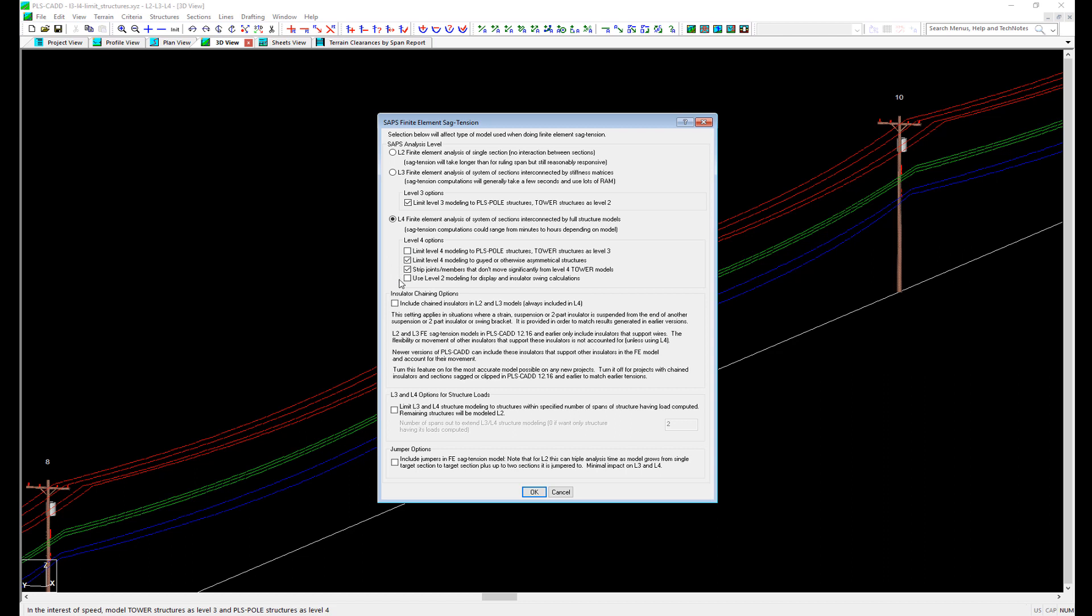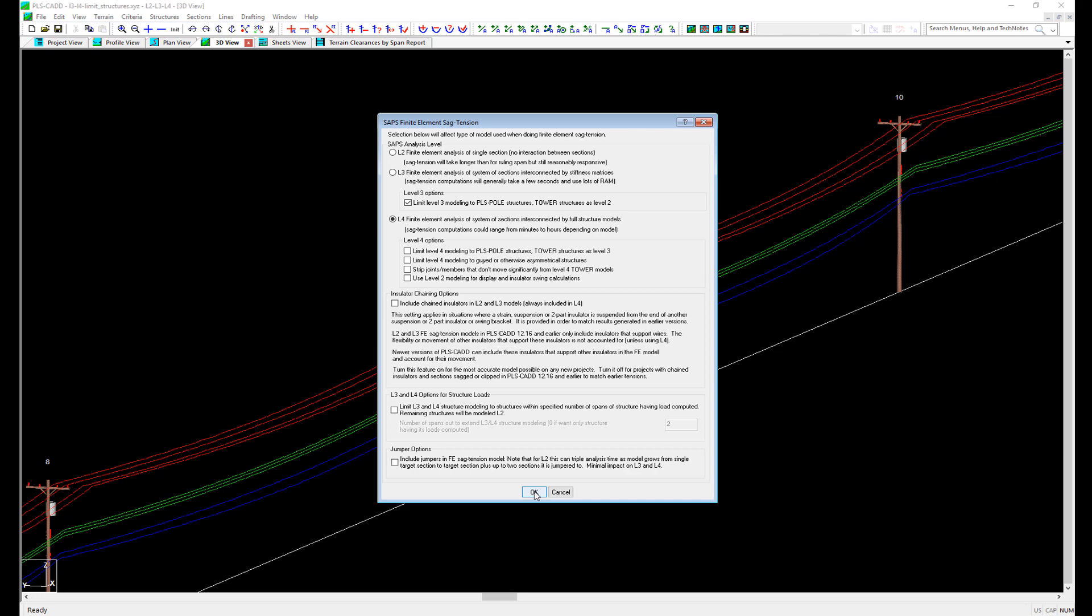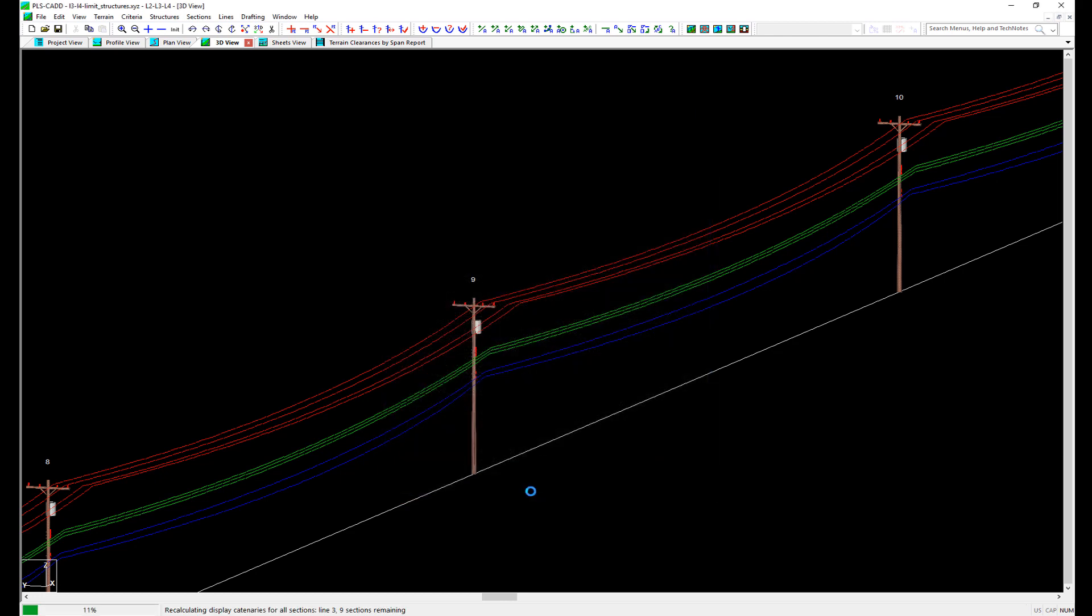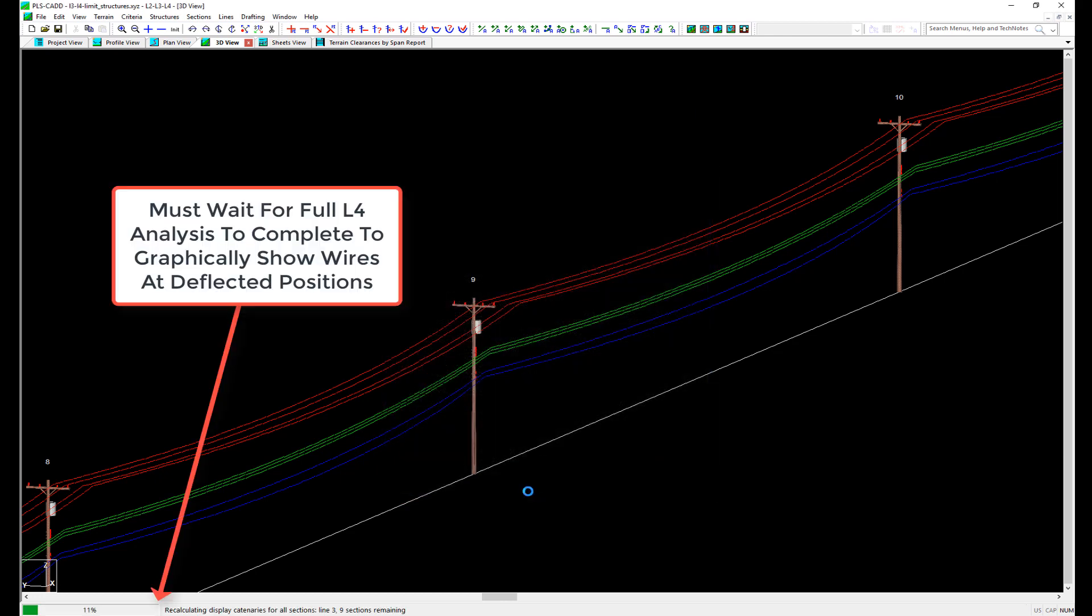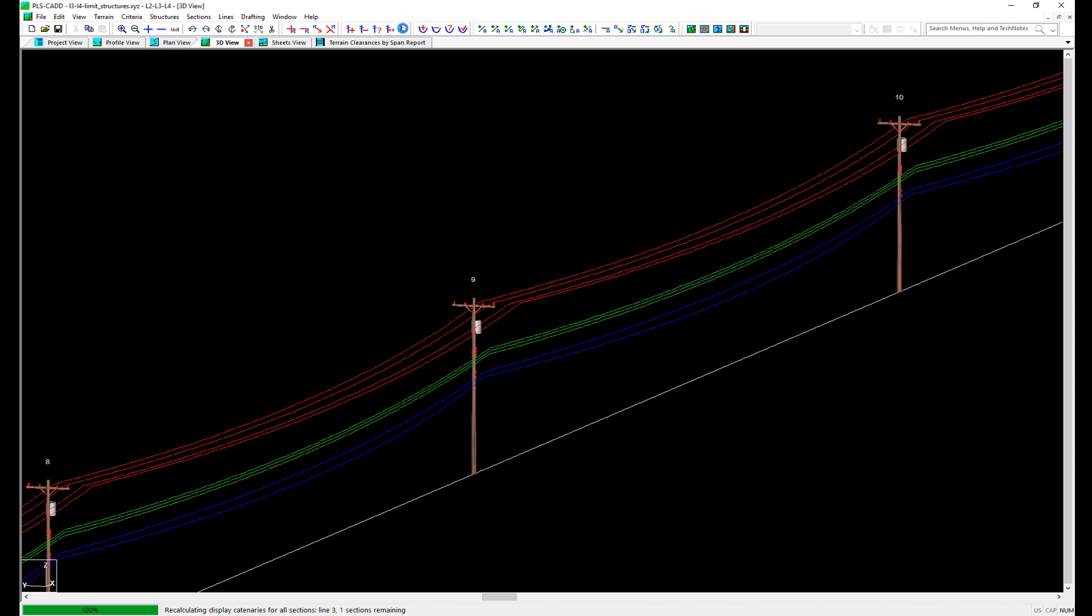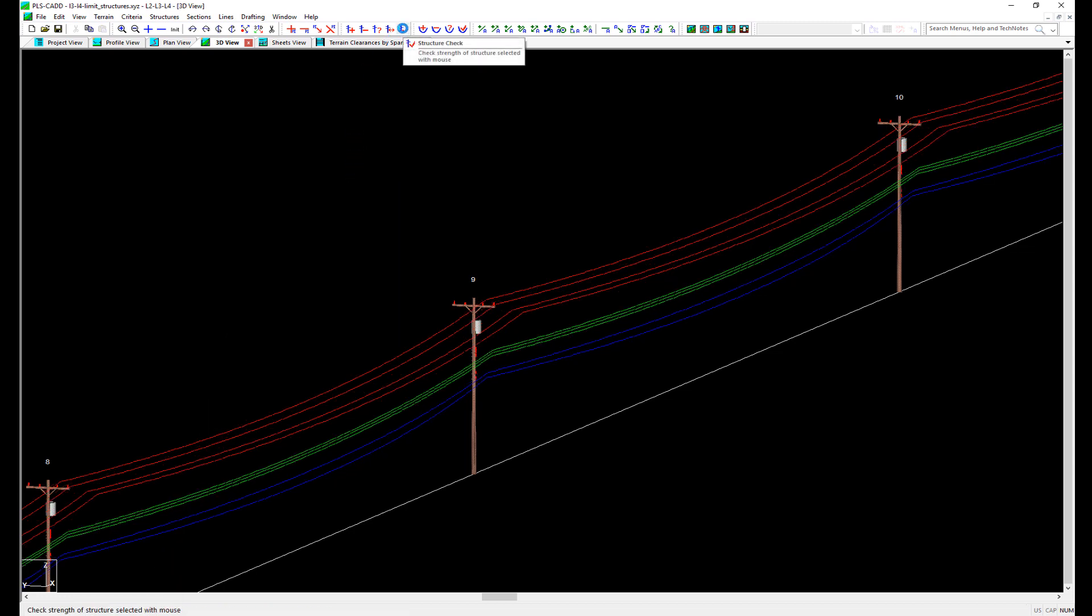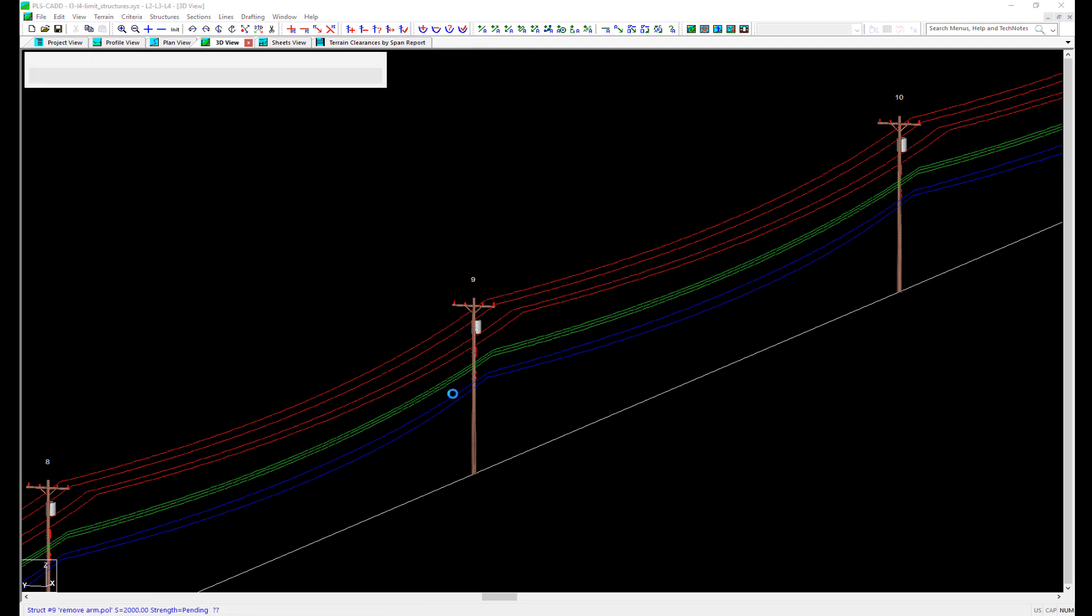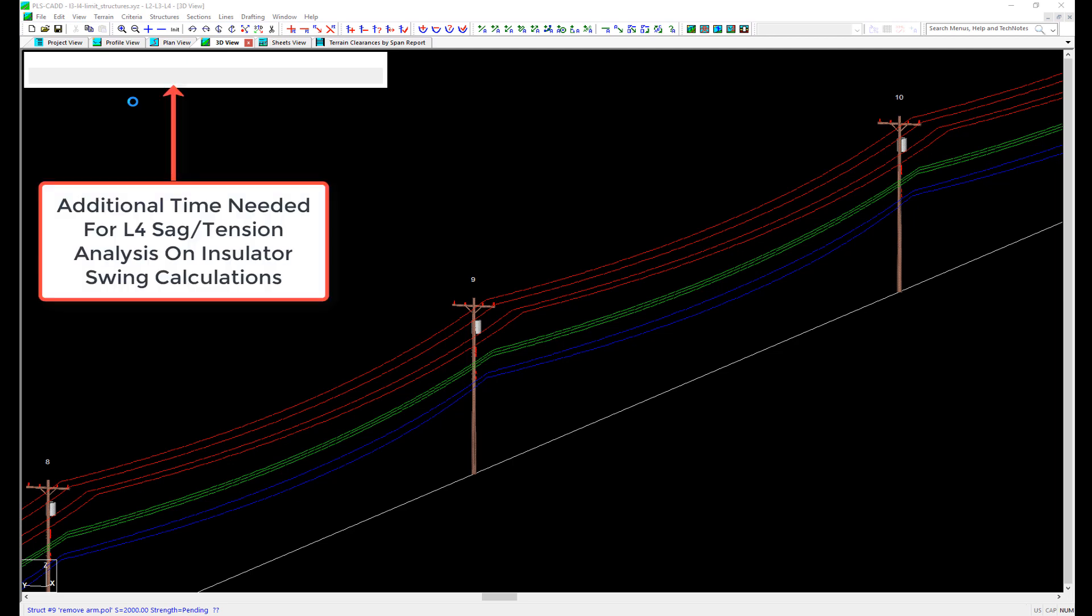The fourth option is a new option added with version 15.50 and can drastically reduce the analysis time. What we found in talking with engineers and designers that are using higher levels of sag tension analysis is that their primary interest is structure loading and analysis. In previous versions, opting for a L3 or L4 analysis meant that all sag tension calculations were performed to this level. This meant that users would need to wait for a sag tension analysis after clicking OK in this dialog box for all sections in the model because a sag tension analysis was needed to show the graphical positions of the wires, considering structure deflection for the entire model at the display conditions. In addition to this, when a structure check was being performed, the insulator swing report was performed using L4 sag tension analysis.